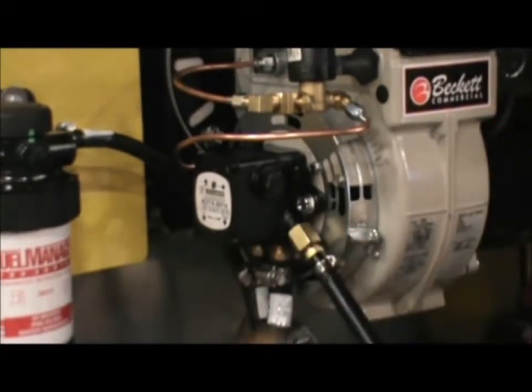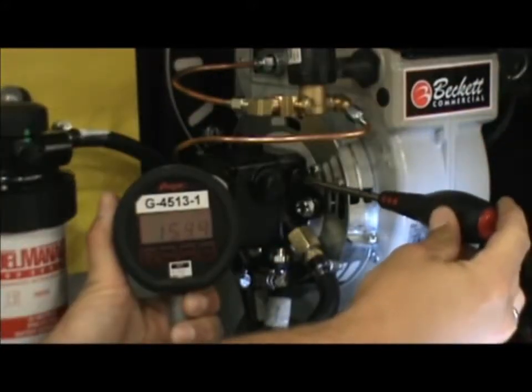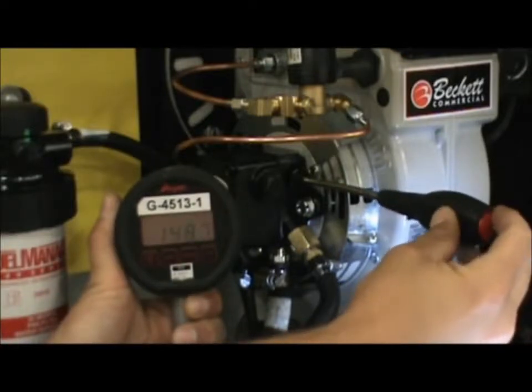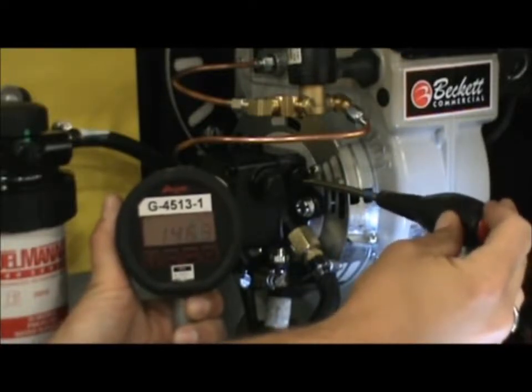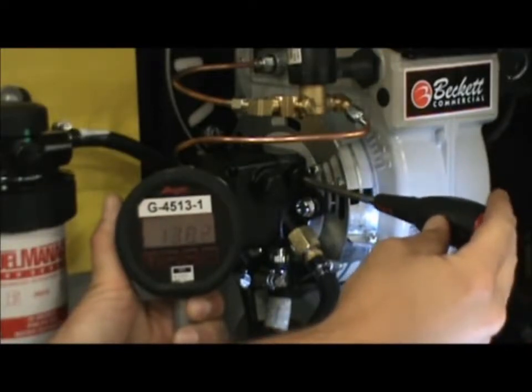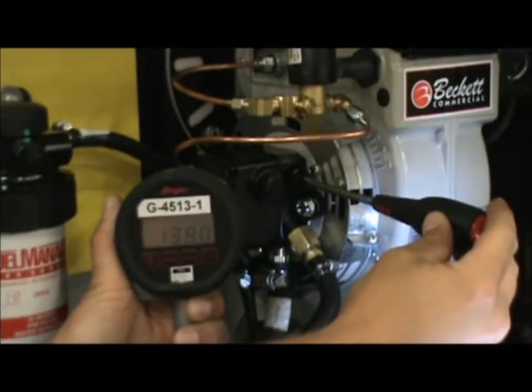Start the burner. To reduce the fuel pressure, turn the adjustment screw counterclockwise to the desired set point. To increase, turn clockwise. Never set the fuel pressure higher than the specifications listed in the Operator's Manual.